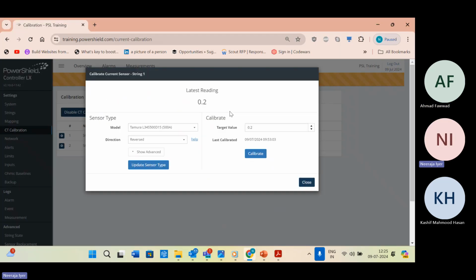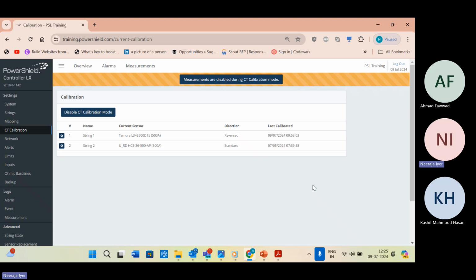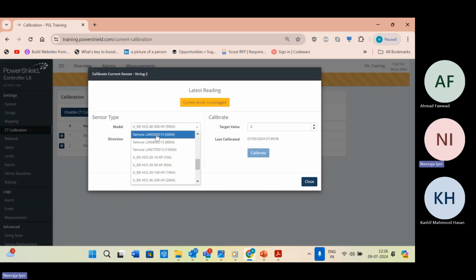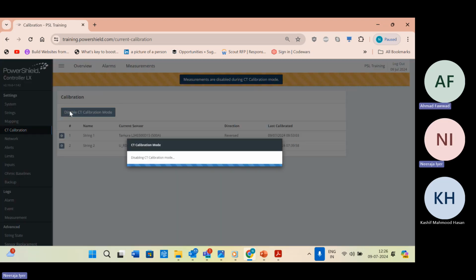So please take a recently calibrated clamp meter and enter the live current value. I know it will be like 0.1 or 0.2, but please don't do this, because sometimes 0.6, 0.8 was also there. I have given reversed for one of the CTs here. For the second one, again I'm going to the settings button, selecting the CT. Suppose this is standard. Selecting standard, it says current sensor is unplugged, because this is the demo site, so I can't do it. That's fine. Once you're done, just disable CT mode, and that's it.